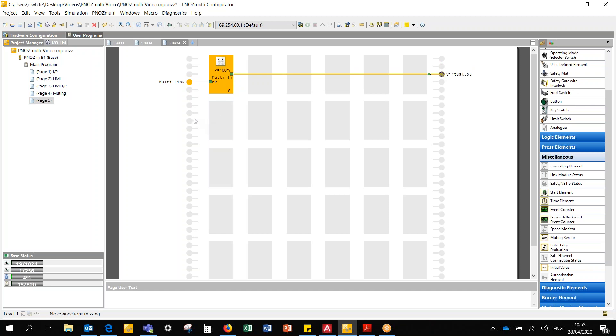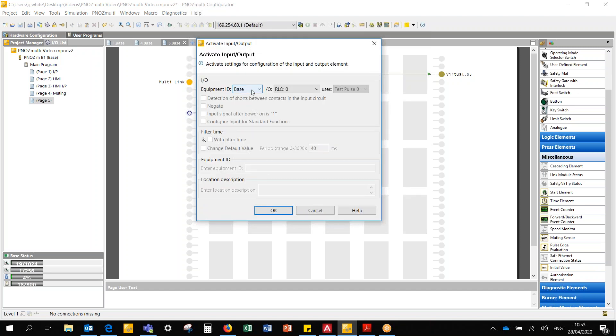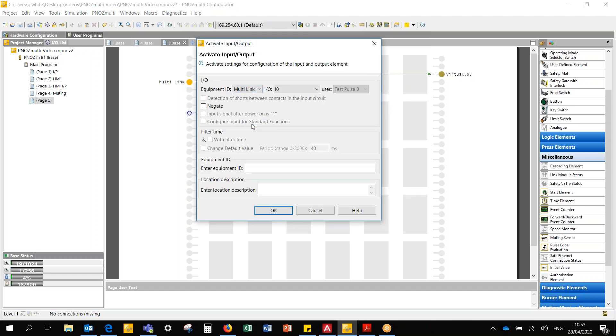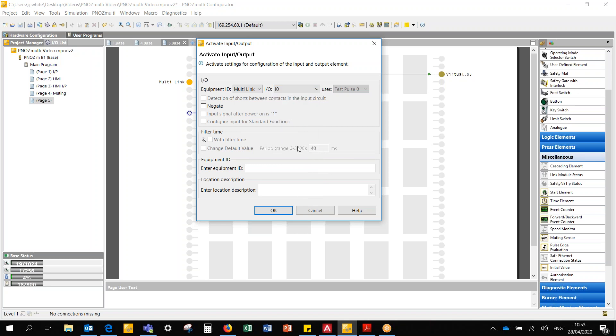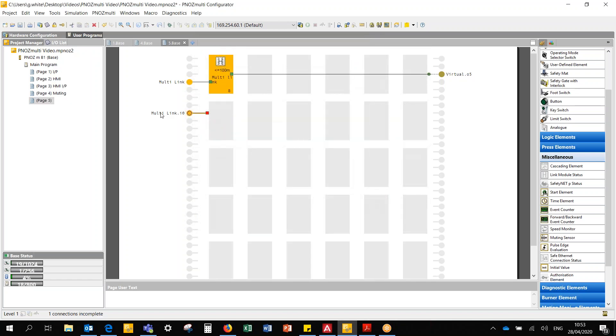I can then use it to send or receive safe inputs. I'm going to say multi-link project and I have an option of I0 to I31. So I have 32 inputs that I can receive. Say input 1, I'll say this is an e-stop coming from my other project.